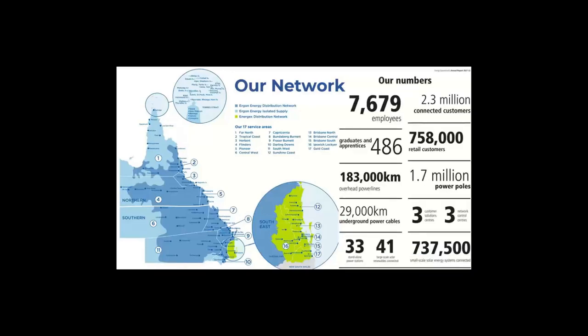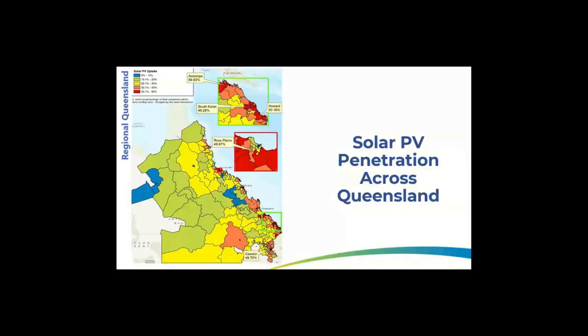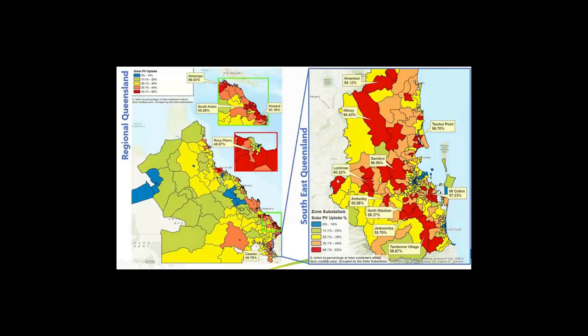We employ over 7,000 people, supply more than 2 million connections. And today we're going to be focusing on the very high numbers of solar PV we've connected in our state. That's resulted in significant penetrations in many of our zone substations. So we're seeing a growing number of areas with more than 50% of connections hosting some level of solar PV. And those penetrations are rising even higher, particularly in the southeast, where there's, I guess, higher population densities. And we're seeing a number of substations now with more than 60% of connected with PV.